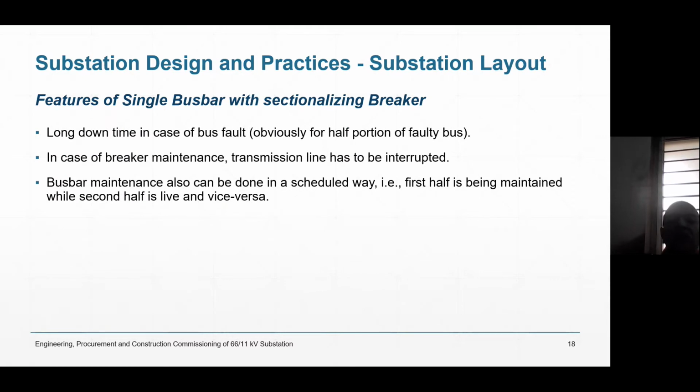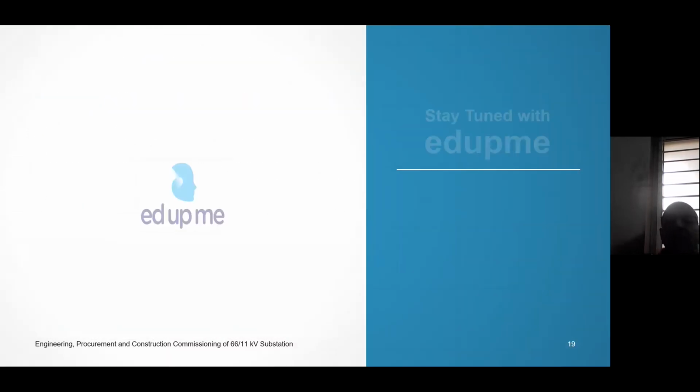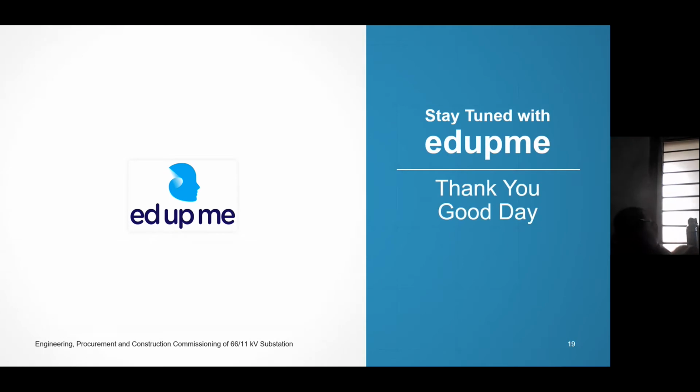So this sectionalizing breaker, we have completed. After having completed sectionalizing breaker, two bus schemes are yet remaining: bus scheme with double bus, and bus scheme with one and half breaker. A little odd. One and half breaker does not mean one breaker and another breaker divided into two parts. It is not like that. One and half breaker scheme means between two feeders, we are using three breakers. So the scheme becomes very costly, but it is a very good scheme. All 400 kV, 765 kV, 1200 kV systems use the one and half breaker scheme. Anyway, about those schemes, we will talk later.